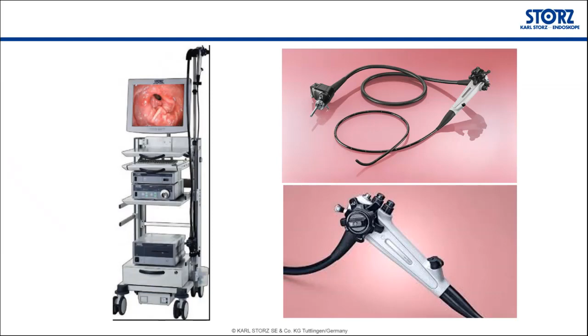Leakage test enables us to show if there is any leakage in the instrument. It means if leakage is there, water may seep inside, and if water goes inside, it will spoil the entire optics. So I would request at the end of the day, kindly do the leakage test. And if in any case you suspect the bending rubber is punctured, or there is some patient bite, please do a leakage test immediately whenever you find this kind of issue, because it is very, very important for the safety of your instrument.